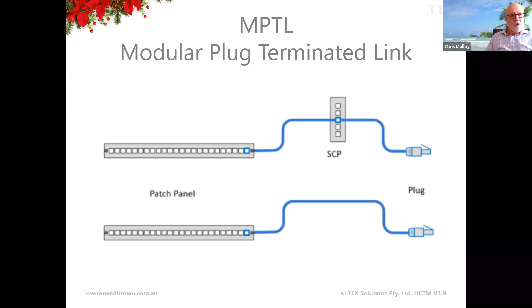New copper testing requirements includes testing for category 8, class 1 and 2 systems. There's also a requirement for balance testing of the cables themselves, and what this TCL stands for is transverse conversion loss. Without going into the detail, what we're talking about here is really a measure of how well balanced the wires are in each individual pair.